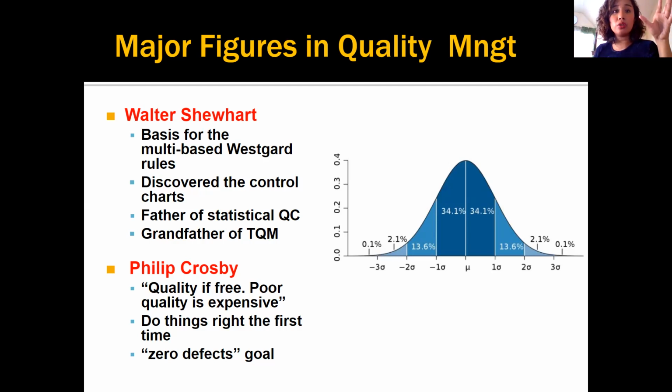It's natural that there are variations in the running of results. It could be because of the equipment, a slight variation in the lamp being used. Because there are many moving parts in processing a specimen. It could be in the pipetting, or the integrity of the reagents or the quality control materials, many variations, okay? And he said that we could use statistical tools to understand these variations, okay?